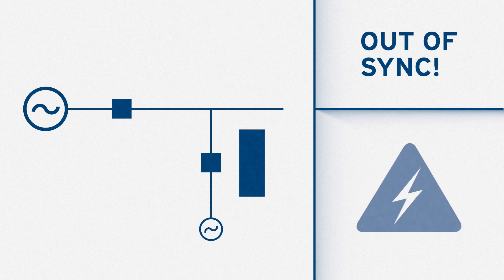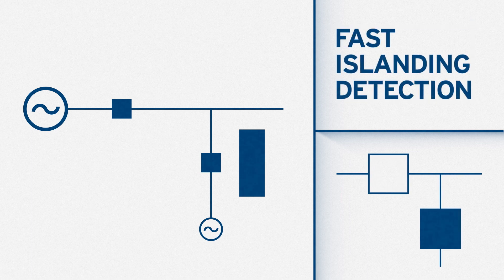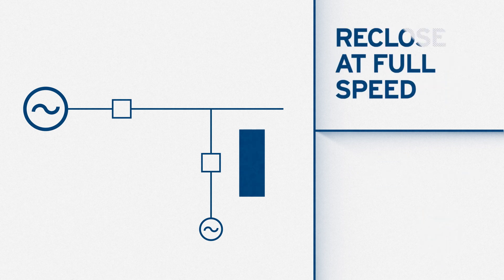The second key requirement is that control solutions have fast islanding detection. They should be able to detect islanding conditions and disconnect the DER fast enough that the utility can still reclose at full speed.